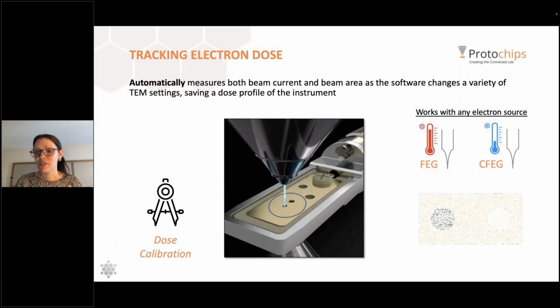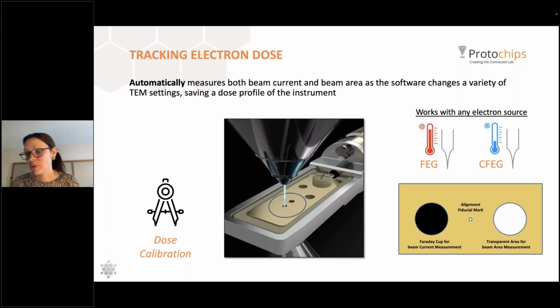And then to calculate those dose measurements, the dose module for the AXON software is what was used there. The module comes with this Faraday cup holder, which allows you to take beam current and beam area measurements for TEM and STEM mode. You set different imaging conditions that you may use, and use the Faraday cup holder to do the measurements under those different conditions and create what's essentially a calibration curve for your microscope. That's all stored in the AXON software as well.